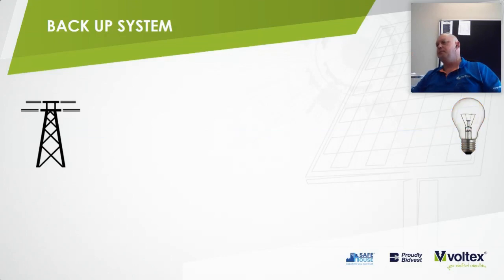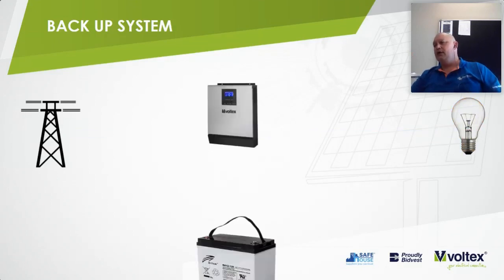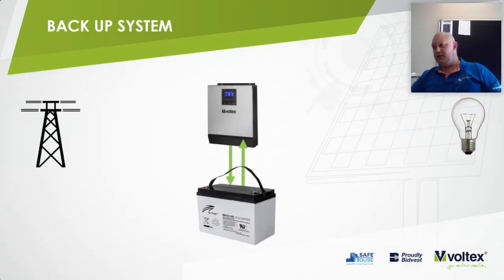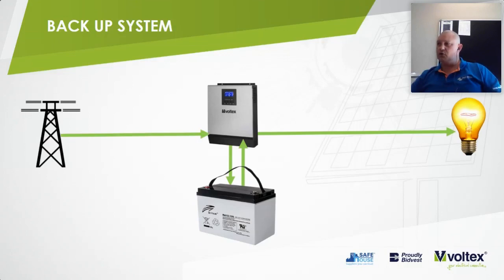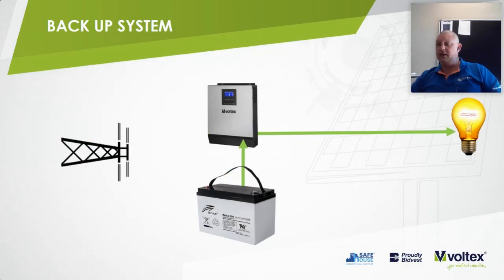Now with the backup system, we add an inverter and battery system into the equation. By tying up the inverter with the battery, it generates AC power, and Eskom or mains can also feed through the system and charge the battery. In the event of a power failure, you will be running purely off the battery system until the mains come back on.